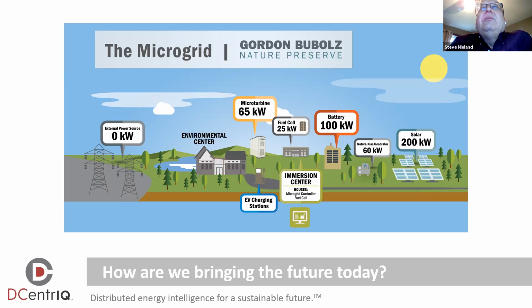We have 200 kilowatts of solar, a 60 kilowatt Kohler natural gas generator, a 100 kilowatt battery, an electrolyzer and a 25 kW fuel cell to utilize the hydrogen from that electrolyzer, and a 65 kilowatt micro turbine located at the lodge itself that we use for combined heat and power on a hydronic system in the lodge.